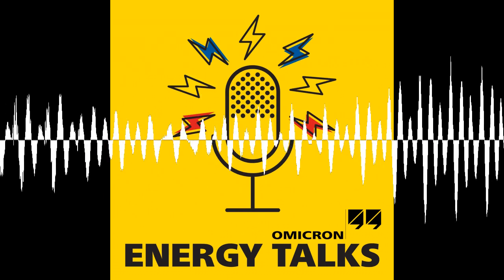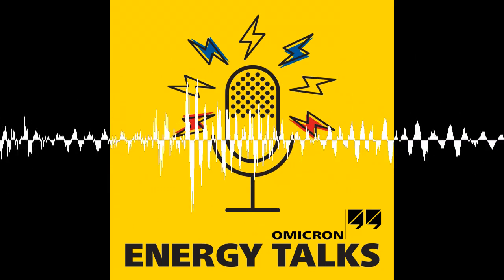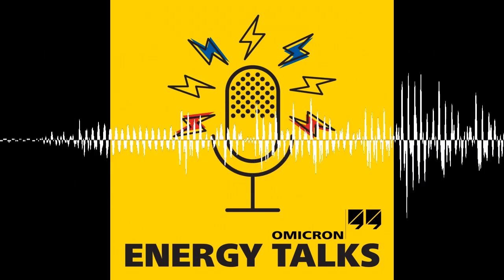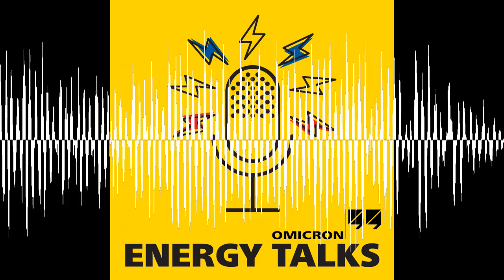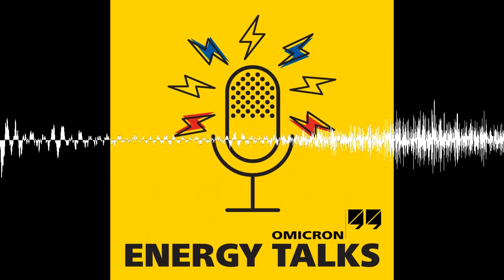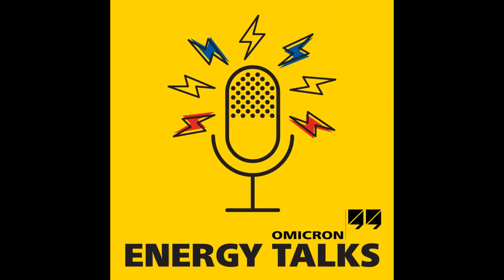I think that when we look at breakers, whether they're just dead tank, we have insulation systems. What is the arc extinction method of that breaker? What is the mechanism? What sort of contacts are they using? Because we know that the contact system from a vacuum breaker is a completely different technology than what's used in a nozzle system in an SF6 breaker. And of course, we have control circuits that could be somewhat different. But for the most part in North America, regardless of the breaker, these apparatus are very similar.